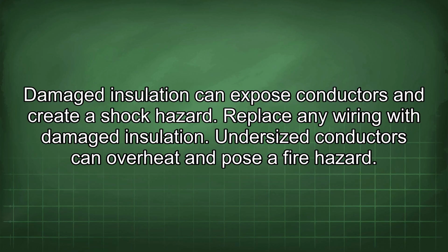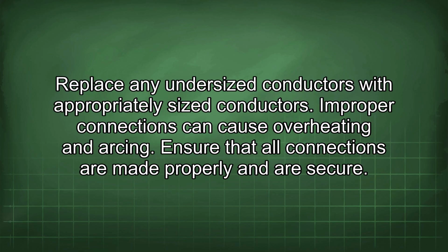Undersized conductors can overheat and pose a fire hazard. Replace any undersized conductors with appropriately sized conductors. Improper connections can cause overheating and arcing. Ensure that all connections are made properly and are secure.